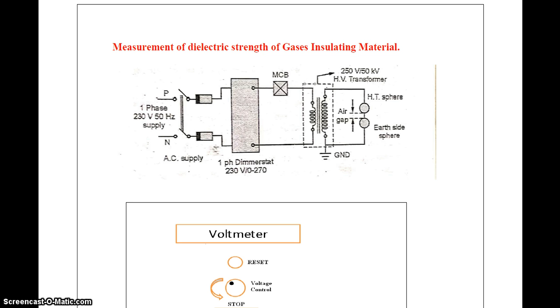Then the circuit diagram of dielectric strength of gaseous insulating material, in which a single phase thermostat or autotransformer is used. Then MCB, and a step up transformer, that is called the high voltage transformer. Then there are two spheres, uniform spheres used: the high tension sphere and the earth side sphere.